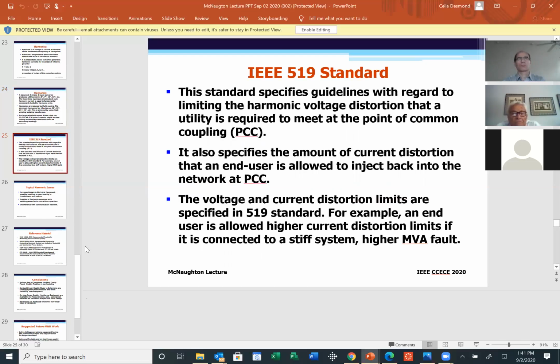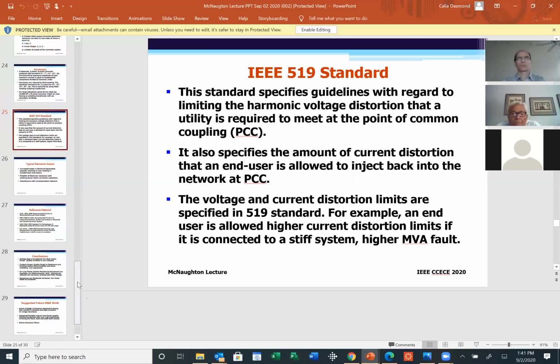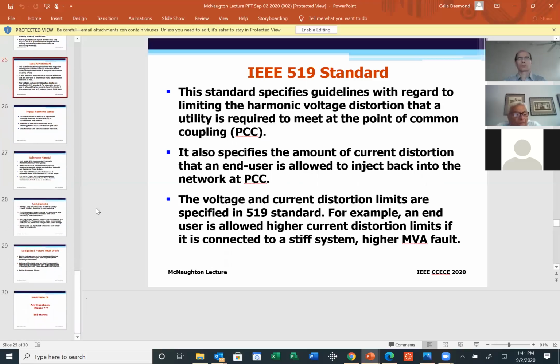This standard 519 is widely used throughout North America. It is like the Bible when it comes to the guidelines for harmonics in our industry. It basically specifies guidelines with regard to limiting the harmonic voltage distortion that a utility is required to meet at the point of common coupling. Now, this standard covers two areas. It places the responsibility on the utility. It tells the utility what voltage quality it can inject to a customer.